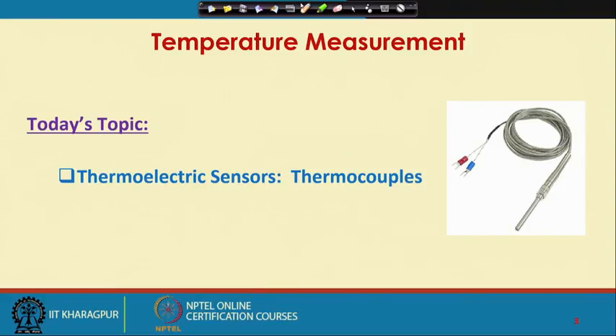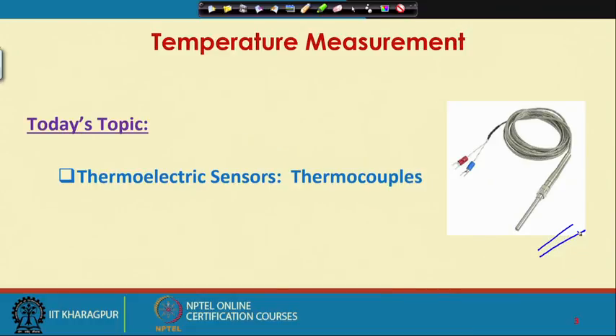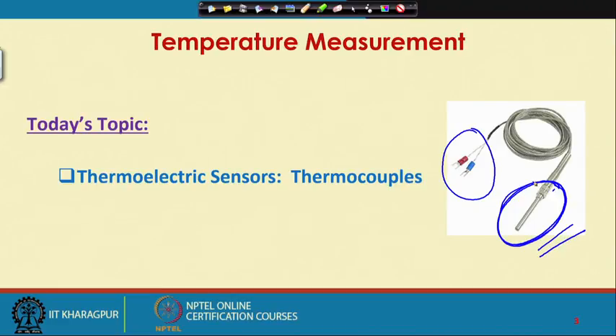Today's topic will be thermocouples. The thermocouple looks like this. What you see basically is a protective case with two leads coming out. This is the thermocouple — it is essentially a protective case. This is introduced into the medium whose temperature you are measuring, and then an EMF, or electromotive force, will be produced. It is a small voltage in the order of millivolts, and that millivolt value will be a measure of the temperature of the medium.